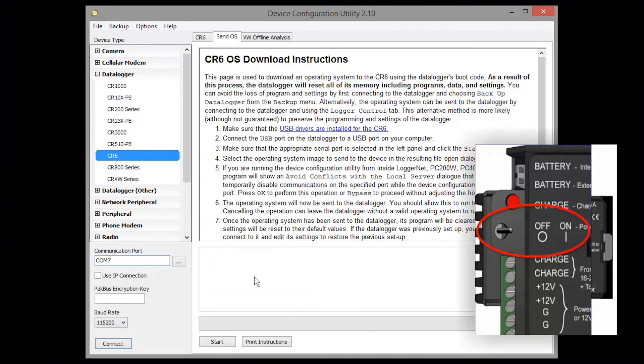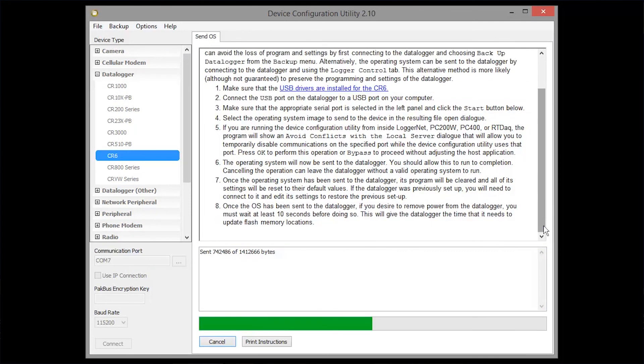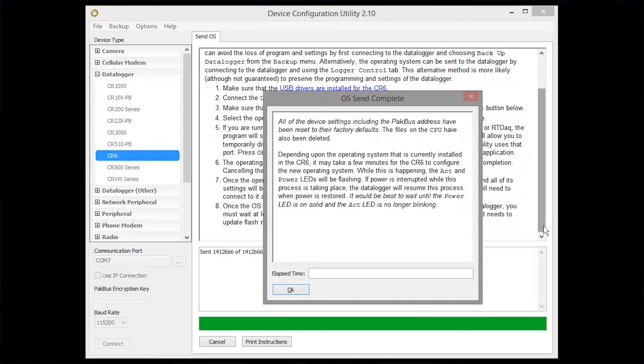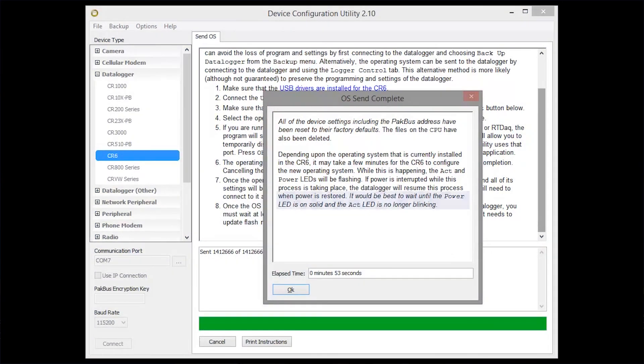This is where the CR1000 and other CR Basic data loggers get powered back up. The time it takes to actually send the OS has been sped up for this demonstration. It will take a few minutes for the data logger to configure the operating system. While this is happening, the activity and power LEDs will flash. Wait until the activity LED is not blinking and the power LED is on solid before proceeding. When it's complete, we'll click OK.